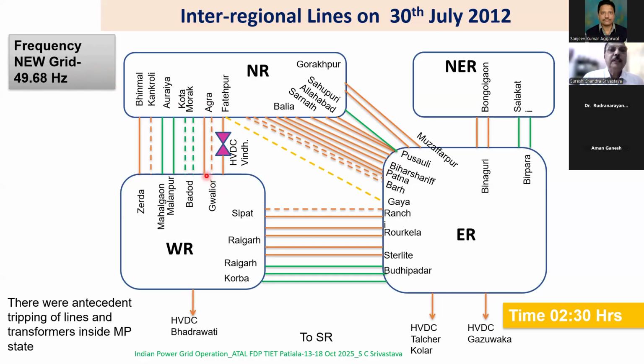As a result, the distance relay operated. Because of the overloading, the voltage was low and current was high, so the impedance seen by the distance relay became low. It came into the zone 3 area, so it operated after some time and tripped this line. So the 1400 megawatt which was flowing through this line was transferred to HVDC and some of the small AC lines, which got overloaded, and they also tripped. As a result, the northern region got separated from the western, and power was flowing through this route. Instead of western supporting northern, it came via the eastern region.